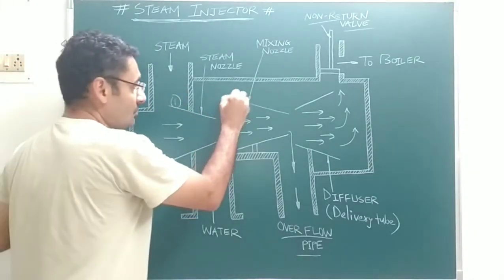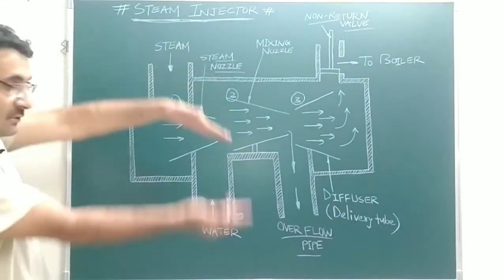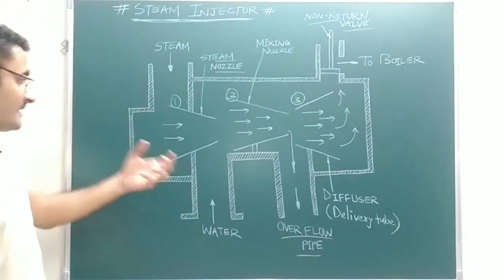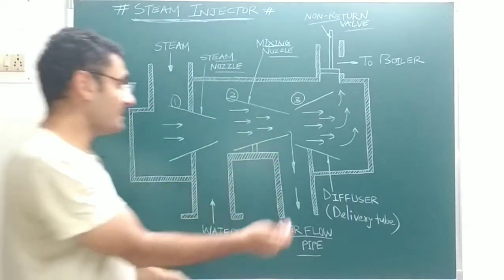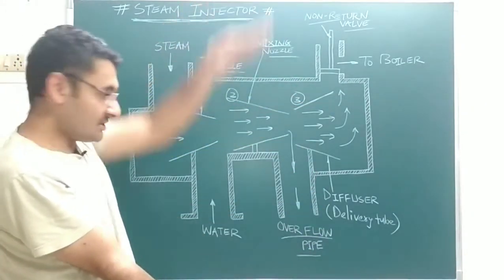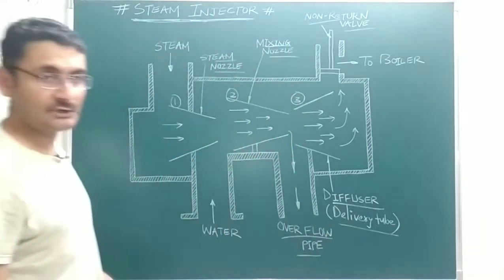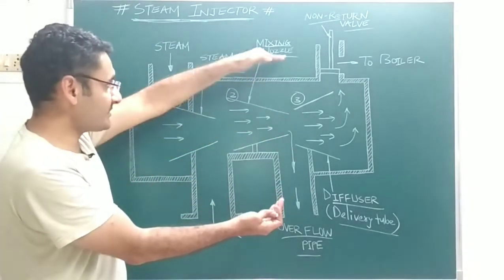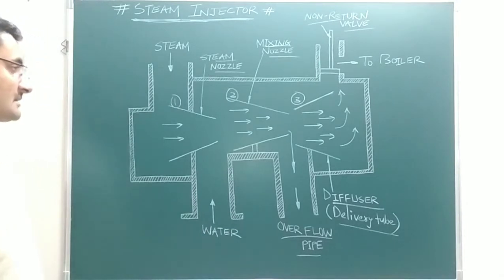There are three cones inside the steam injector. The first cone is the steam nozzle, which is a converging nozzle. The second cone is the mixing nozzle, which is also a converging nozzle. The third cone is the opposite — a diverging nozzle, also called a diffuser or delivery tube. So: first is the converging steam nozzle, second is the converging mixing nozzle, and third is the diverging diffuser.